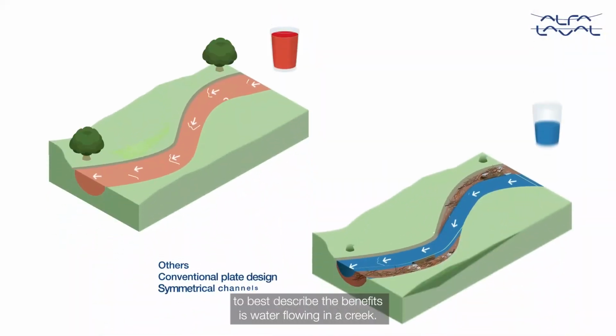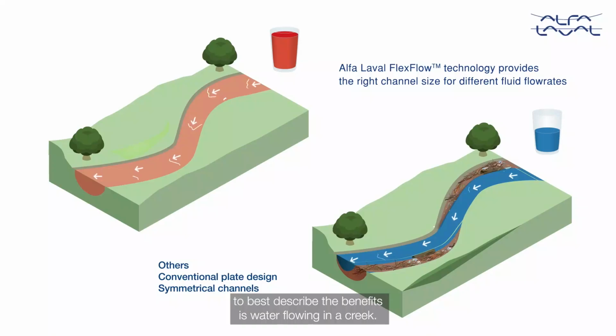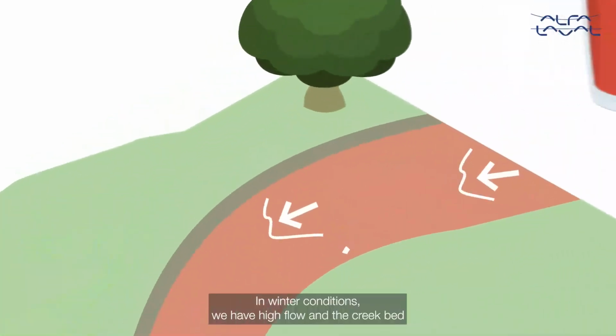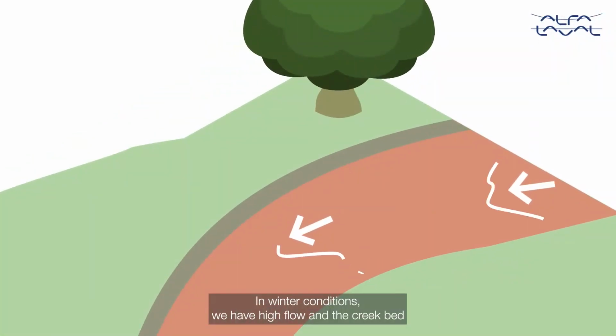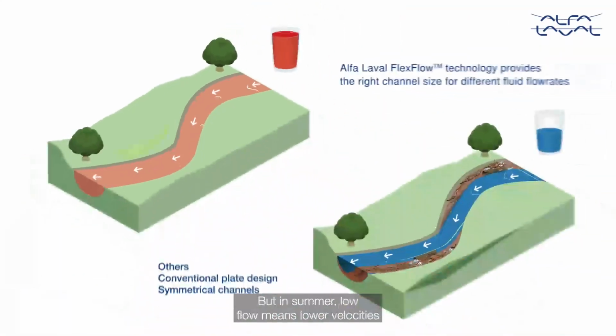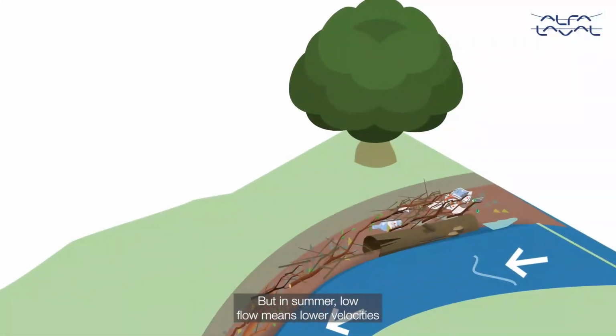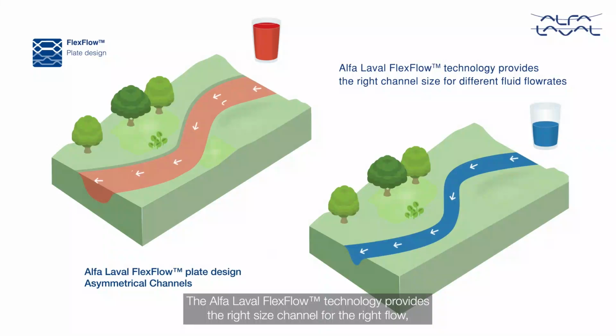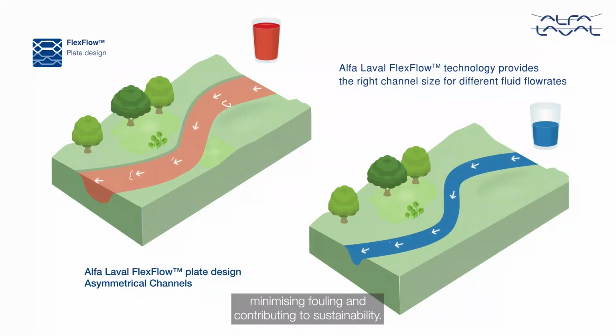A metaphor to best describe the benefits is water flowing in a creek. In winter conditions, we have high flow, and the creek bed is perfect. But in summer, low flow means lower velocities and accumulation of debris. The Alfa Laval FlexFlow technology provides the right size channel for the right flow, minimizing fouling and contributing to sustainability.